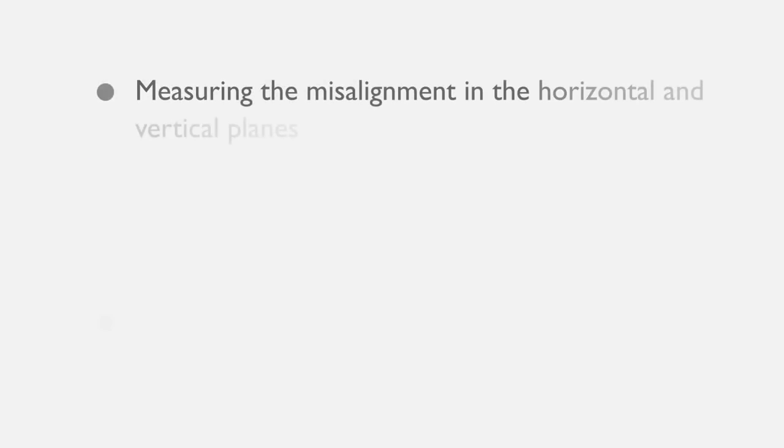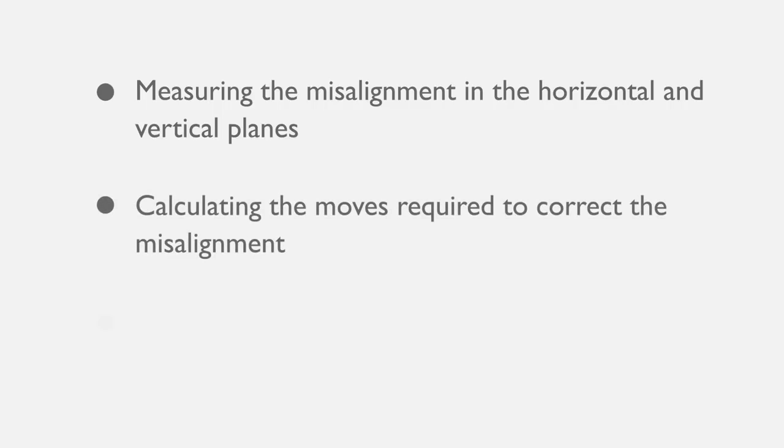The challenge of precision alignment can therefore be defined as, first, measuring the misalignment in the horizontal and vertical planes, second, calculating the moves required to correct the misalignment, and finally making the prescribed adjustments.